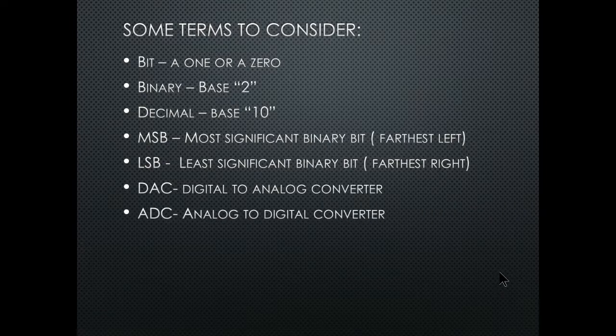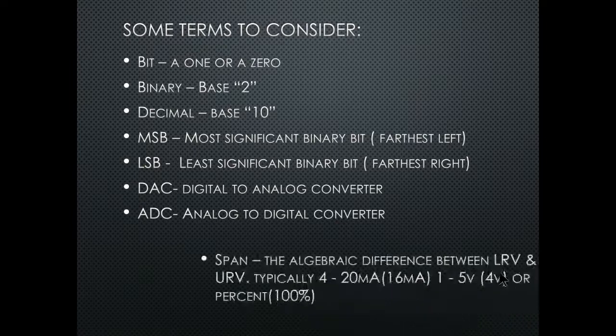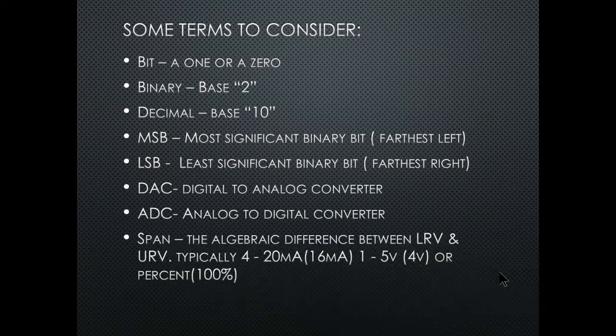DAC is digital to analog converter; ADC is analog to digital converter. Span is the algebraic difference between the lower range value and the upper range value — for us mostly 4 to 20 milliamps with a 16 milliamp span, 1 to 5 volts with a 4 volt span, or 0 to 100 percent.